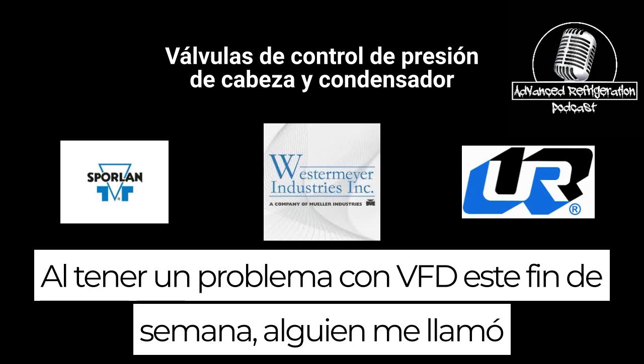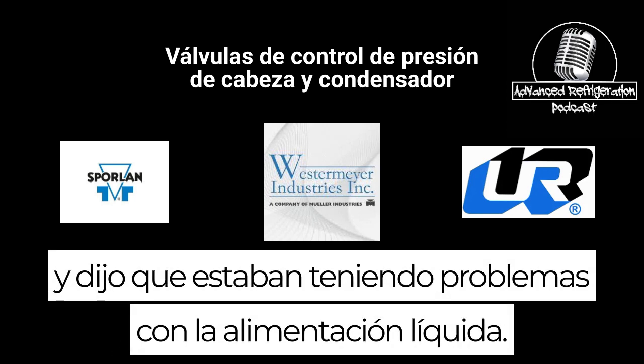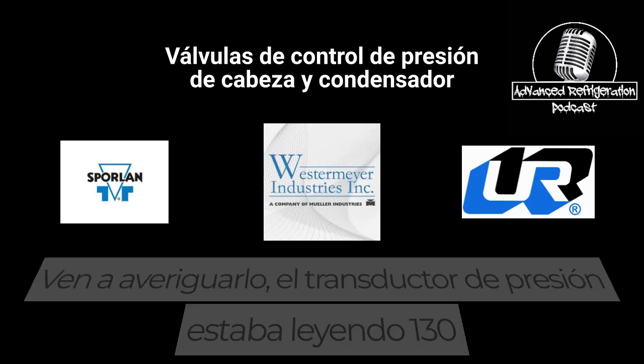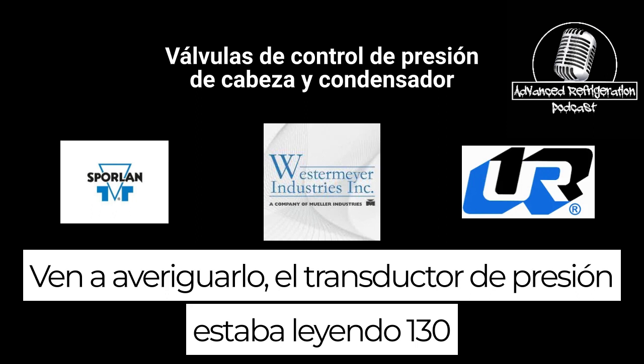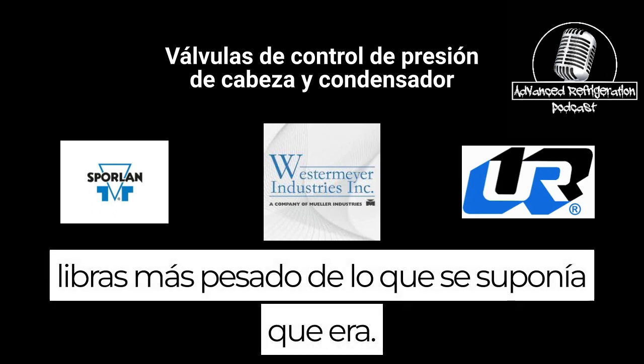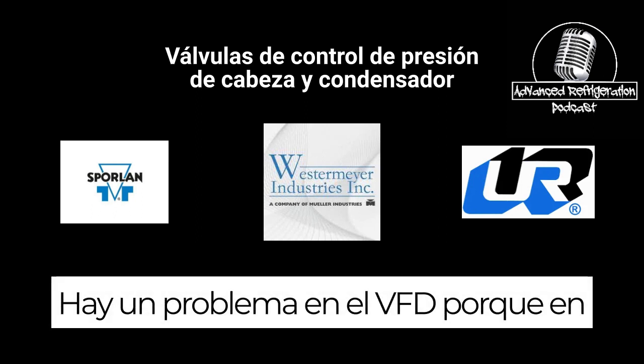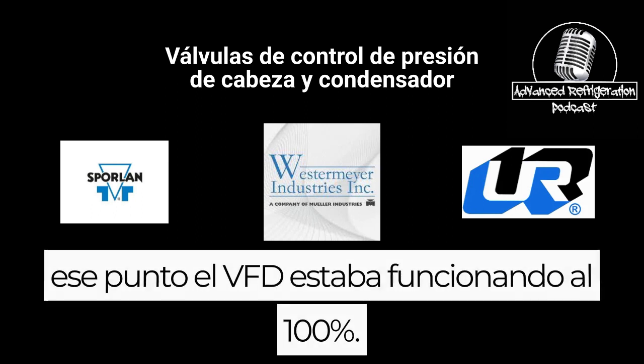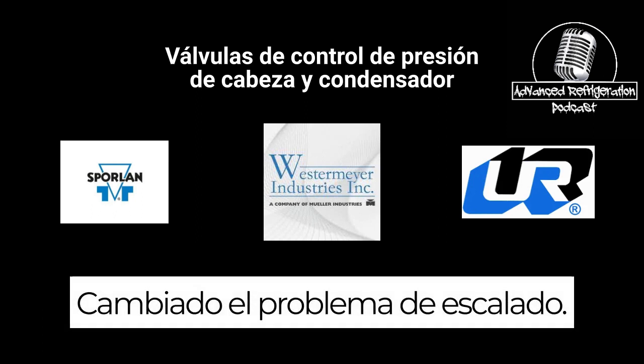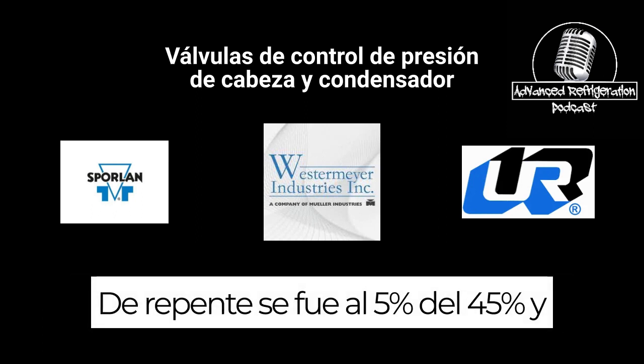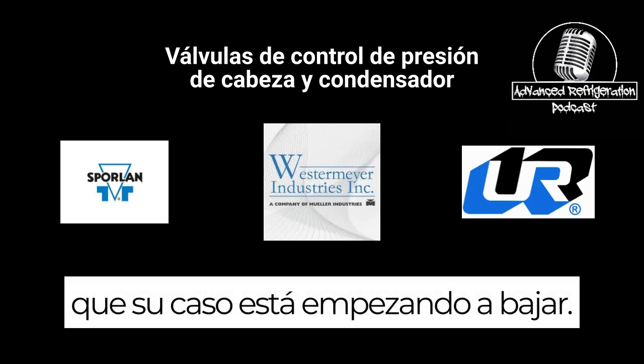This weekend, someone called me up and said they were having liquid feed issues. Come to find out, the pressure transducer was reading 130 pounds higher than it was supposed to. There was a scaling issue on the VFD, because at that point the VFD was running at 100%. I changed the scaling, and all of a sudden he went from having 5% receiver up to 45%, and his cases started to come back down.